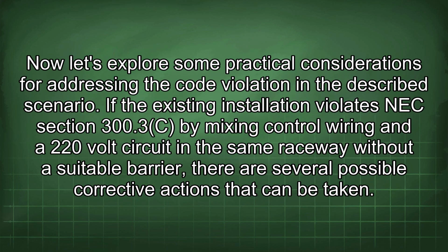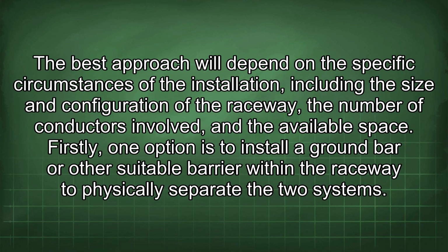Now let's explore some practical considerations for addressing the code violation in the described scenario. If the existing installation violates NEC Section 300.3(c) by mixing control wiring and a 220-volt circuit in the same raceway without a suitable barrier, there are several possible corrective actions that can be taken. The best approach will depend on the specific circumstances of the installation, including the size and configuration of the raceway, the number of conductors involved, and the available space.